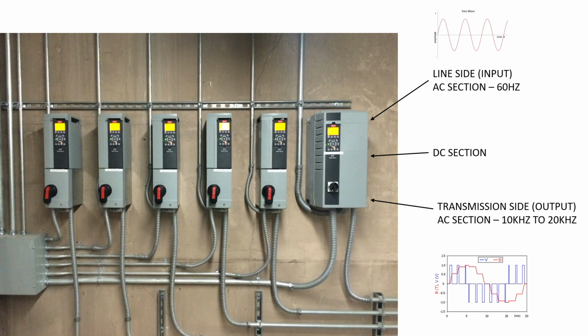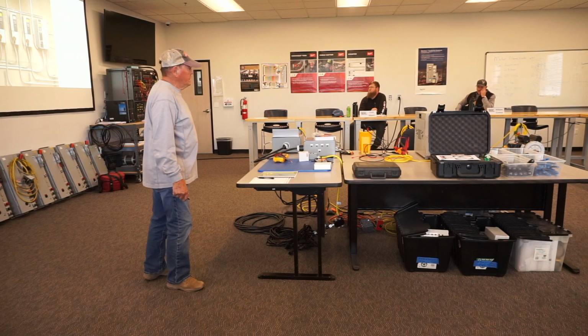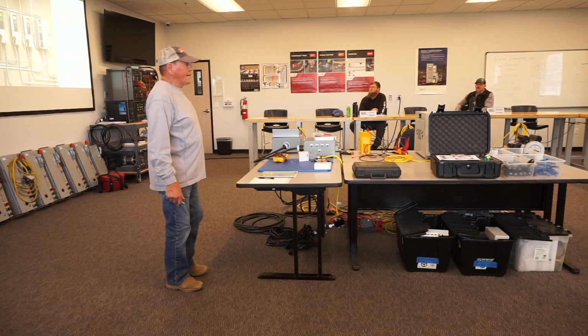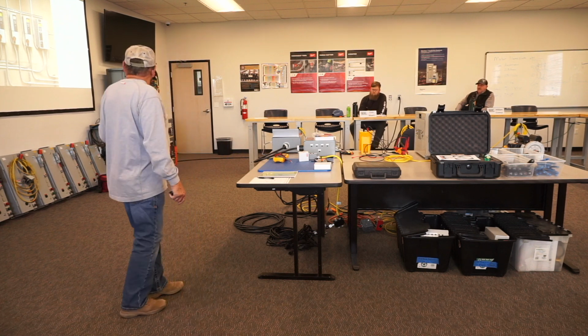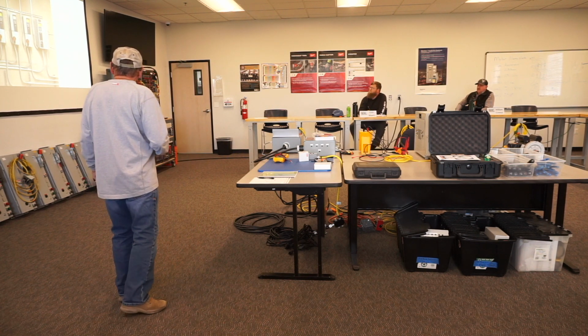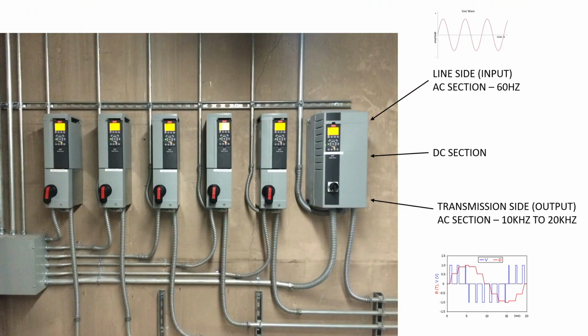It can be anywhere from probably, they're lowering it down to about 4,000 hertz, I think now, up to 20,000 hertz based on manufacturer. So to me, that's transmission speed. 15,000 and lower is RFI, radio frequency interference, and 15,000 and above is EMI, electromagnetic interference. So you're in the transmission zone here. And the output, basically, we'll go through all of this, is not a sine wave. It's a square wave. If you have any questions, fire them out there.